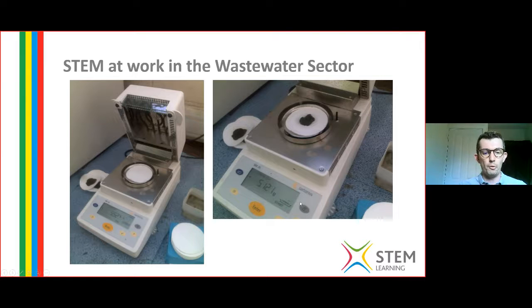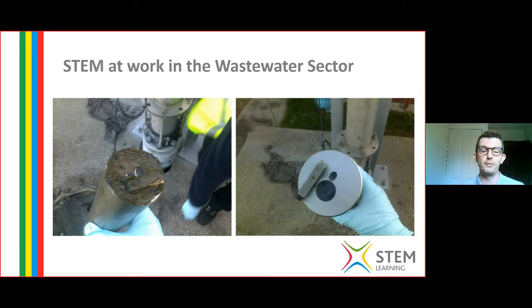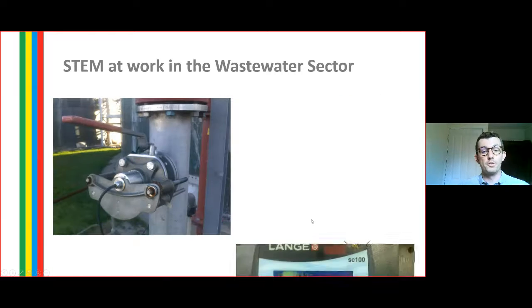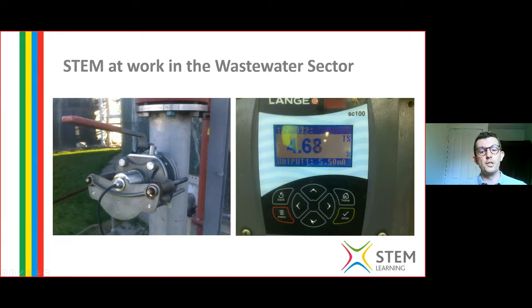But before the instrument is put back into service, the sludge needs to be cleaned from the transducer. This is a maintenance task carried out by maintenance technicians as well as operational technicians on a periodic basis. The dry solids instrument's output is used in a process control system to ensure the sludge is at optimal thickness for the anaerobic digestion process.